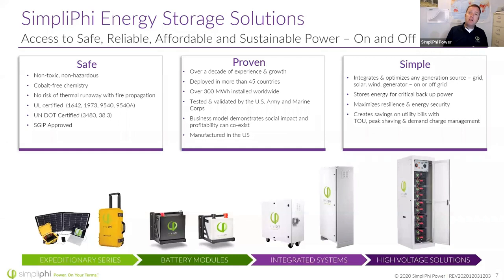One thing we've always been known for is having a battery that is inverter agnostic. You can take one of our batteries and use it with whatever you like — a SolarK, a Schneider, a Victron, a Morningstar, a Samlex. As long as you get into that inverter or charge controller and adjust the set points — like the low battery cutoff, the float, the bulk voltages, the maximum discharge or charge currents — you can use our batteries. We have integration guides that help you program those other pieces of equipment.